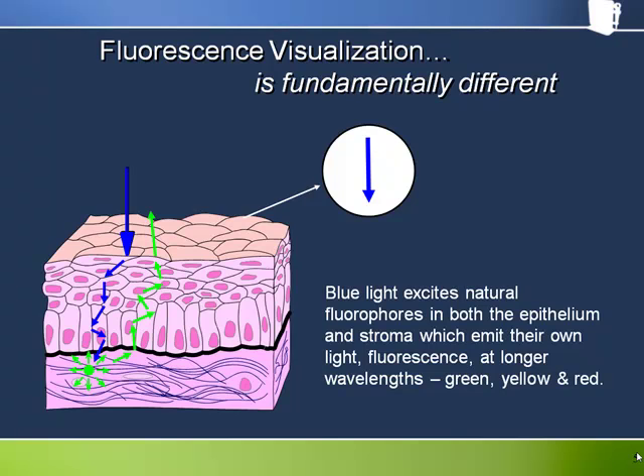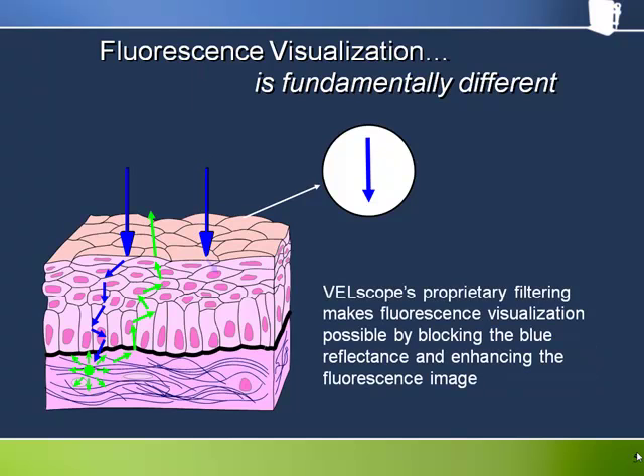These fluorophores absorb the blue excitation light and then re-emit light at a longer wavelength — that is, green, yellow, or red — a fraction of a second later. Blue light excites fluorophores in both the epithelium and the stroma. The natural fluorescence from the tissue is relatively weak, much less bright than the blue reflected light. The Velscope handpiece allows us to see the natural fluorescence by blocking the much brighter blue light reflected back from the tissue. Proprietary filtering of the fluorescence light is also performed to optimise the contrast between normal and abnormal tissue.